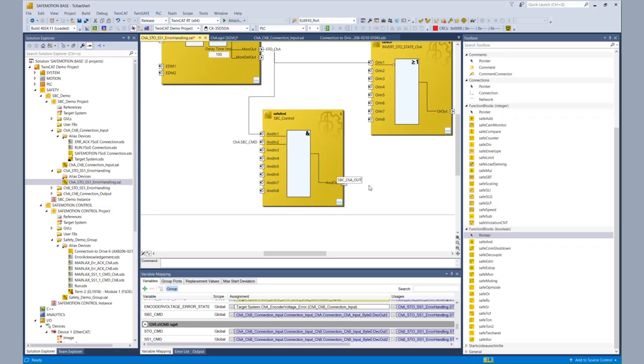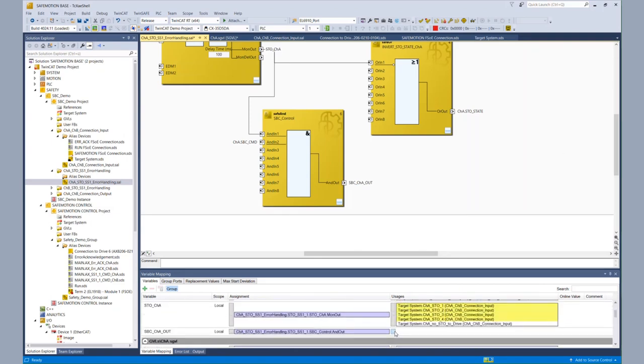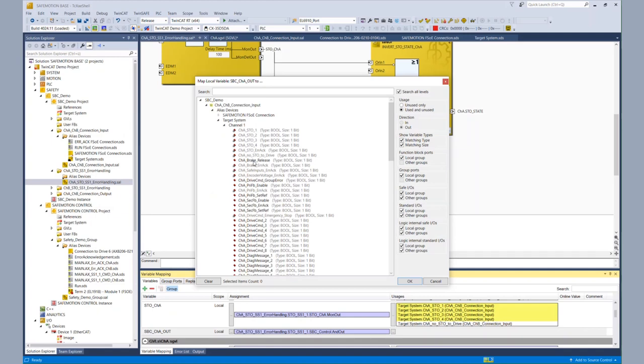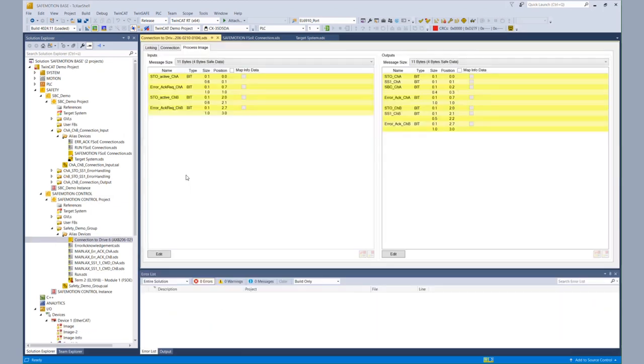We assign it to the SBC bit within the process image, so we go to the variable mapping, go to the variable SBC channel A out, and choose the alias device target system — it goes to the local process image of the AX8000 — and choose channel A brake release. Basically that was all the basic configuration on the AX8000 side. We are receiving the SBC command from the EL6910 and in combination with our STO output we are controlling the SBC — the safe brake control.